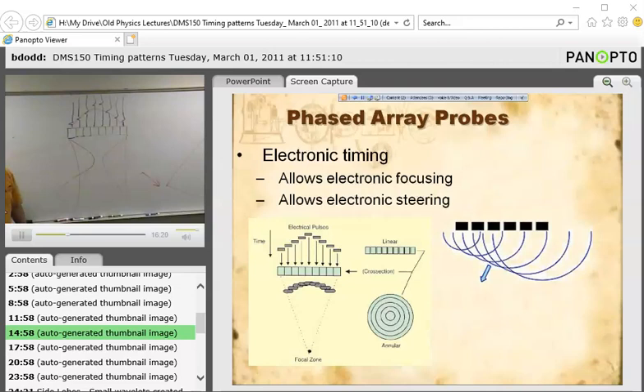Does that make sense on why it does that? It's basically a big wave, and it's all moving into a point. All right? We normally think of a wave, if you drop a pebble into a pond, it spreads out. But if you take a large wave and you focus it at one point, all parts of the wave, and it's all traveling this way, then it's going to get to this point sooner. So now we've moved our natural focal zone, our NZL, from way down here up to here by changing the pattern of the firing of the crystals. All right? So now we can electronically change where we focus our sound beam. Not just by the diameter of the crystal, but also by the timing of it.